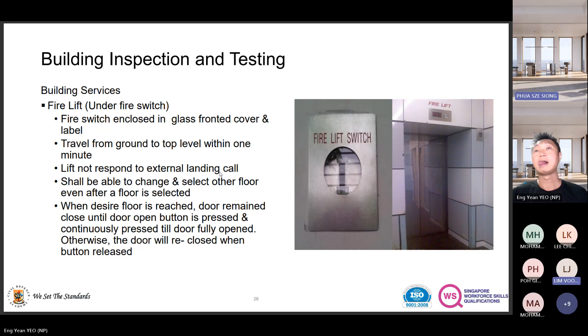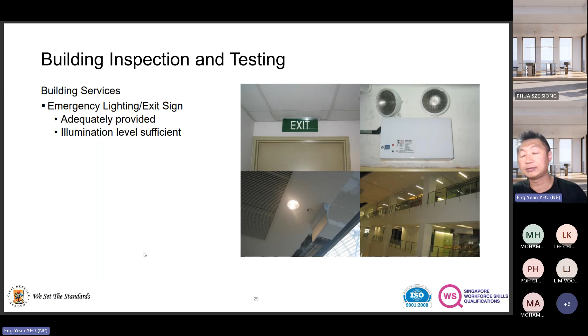Right, so exit light illumination level sufficiency - usually what they do when testing is check whether you have a minimum of 0.5 lux on the floor, to make sure it can last for an hour. All the emergency lights will be tested, but usually they won't test for a full hour - they'll let it go around, then the QP will walk around, and based on their estimation, if they think it's sufficient, then it passes. Exit light is also important because this is something that's always ignored. Nobody cares about it, but when you really become an FSM, that's where we need to check and remind - whether it's the landlord or the tenanted unit - if we see this is not operating, just ask them to rectify the problem.